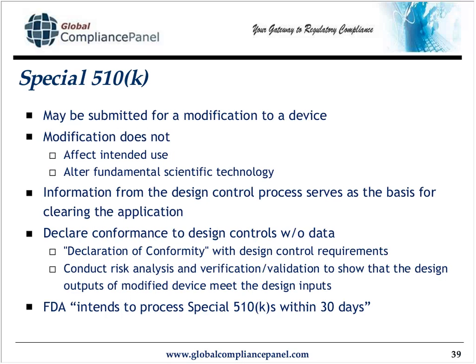A special 510K, as opposed to traditional, is one that you could submit for a modification for a device as long as your modification does not affect the intended use or alter the fundamental scientific technology. This is probably the reason why most of us limit our special 510Ks to product line expansions or new devices that we ourselves are manufacturing. Because how can we possibly know what the fundamental scientific technology of a device is unless we design and/or manufacture it? You use the information from your design control process to clear the application.